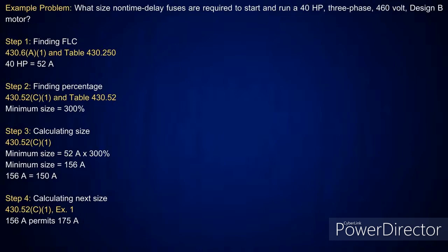So I look at table 430.250, I pick up 460 volts, come down, pick up 40 horsepower. It's going to tell you it's good at 52 amps. So now I'm going to go back and look at table 430.52, and I come down and I'm looking at a non-time delay fuse, squirrel cage. It's going to tell me take it at 300%. So I'll just take the 52 amps at 300%. That's going to give me 156 amps.